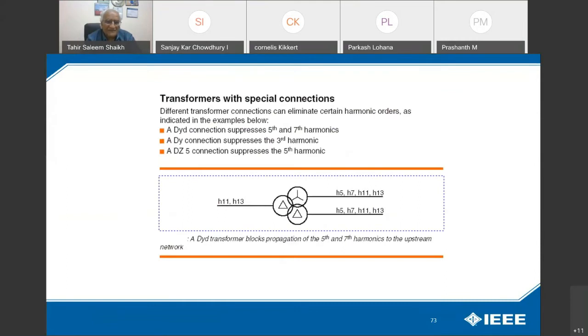These are split transformers. I have seen that, but in spite of that there is still a lot of problem. A Delta-Delta connection suppresses the 5th and 7th harmonics, which are the important harmonics generated from a VFD. A Delta-Wye connection suppresses the 3rd harmonic, which is the important phenomenon for a UPS, and a DZ5 connection suppresses the 5th harmonic, for VFDs and UPS both, whatever it may be. So you can see the UPS in positive direction gives you the harmonic current, a third harmonic. This third harmonic means a multiple of the base frequency. Fifth harmonic and seventh harmonic also mean multiples of the base frequency.